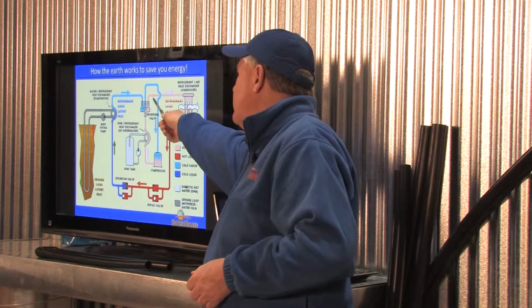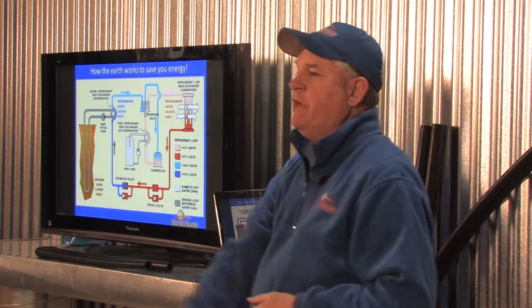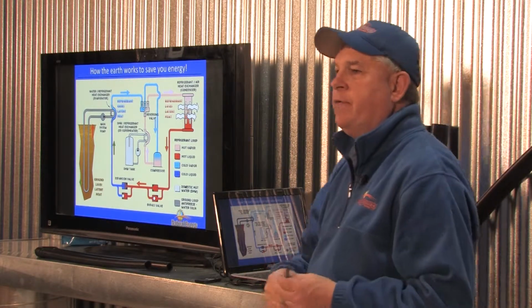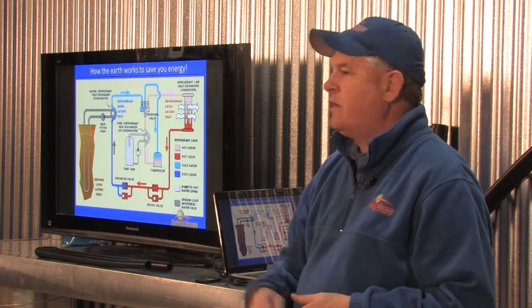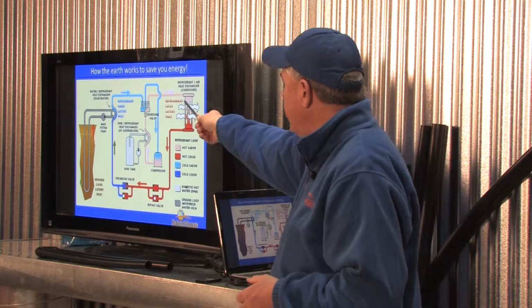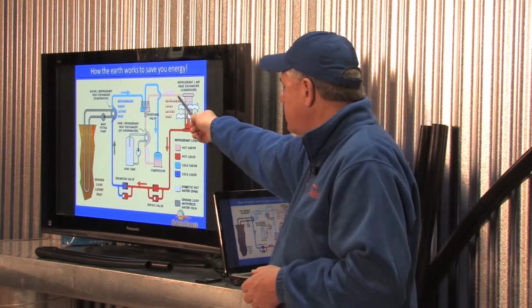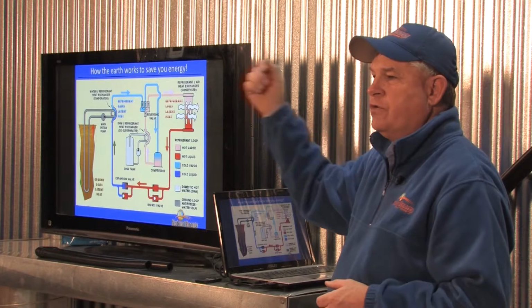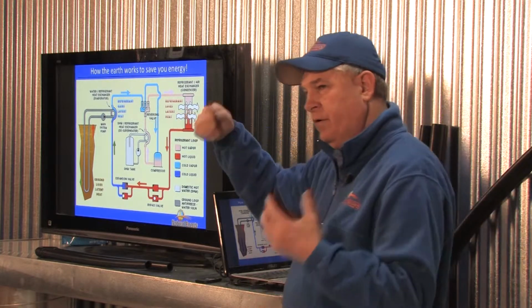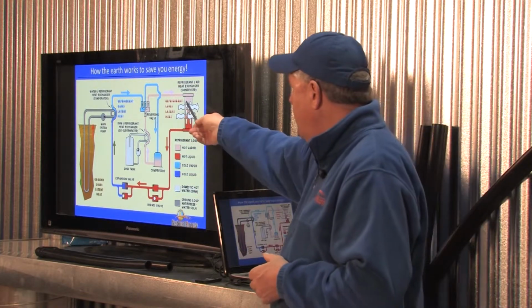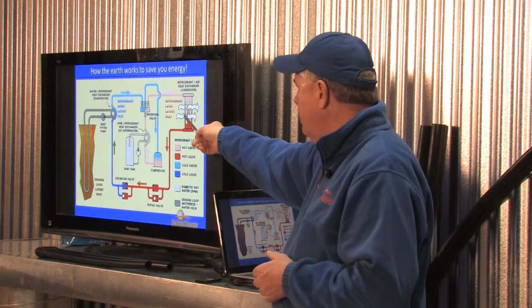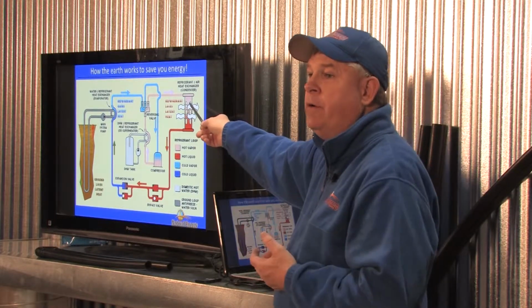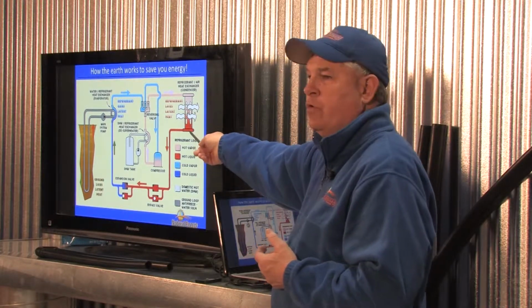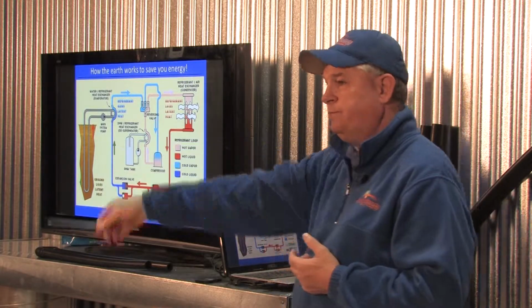Now the hot gas travels up and goes into the heat exchanger. The heat exchanger is just basically a big radiator. It's what's in that box right behind the air filter. So we have hot gas going in the top, and we have the cooler air circulating through the house. Same thing, energy flows downhill. The energy from the refrigerant flows into the air or water. The refrigerant cools off, the air warms up.